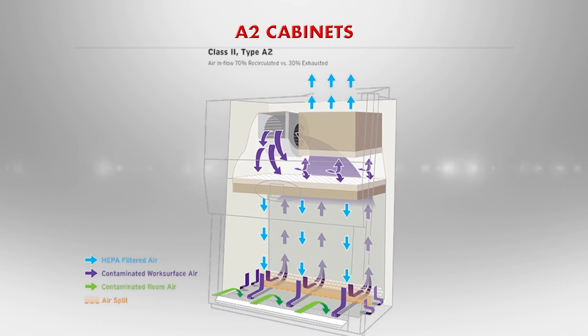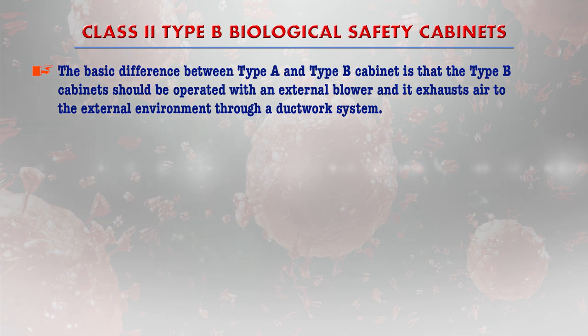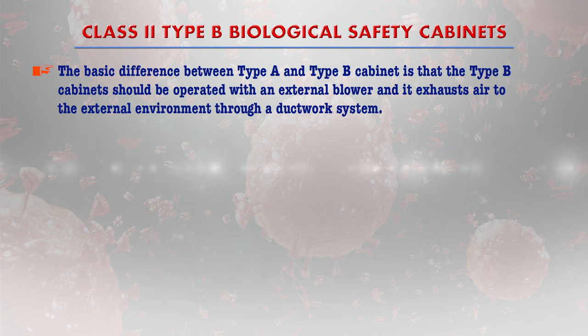In the type A2 cabinet, 70% of the air from the positive plenum is recirculated as downflow and the remaining 30% is discharged to the lab through the exhaust filter. The basic difference between type A and type B cabinets is that type B cabinets must be operated with an external blower and exhaust air to the external environment through a ductwork system. The ductwork system, air pressure, and filtration are all important factors distinguishing these cabinet types.